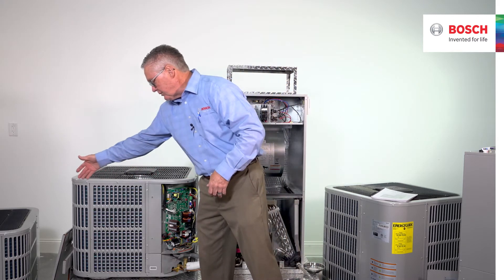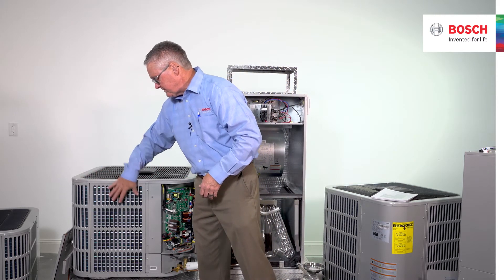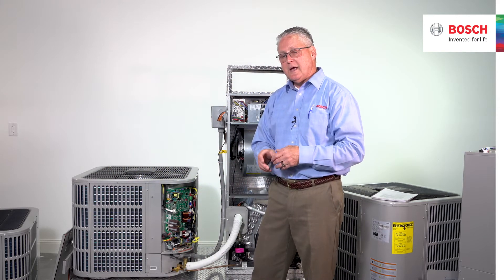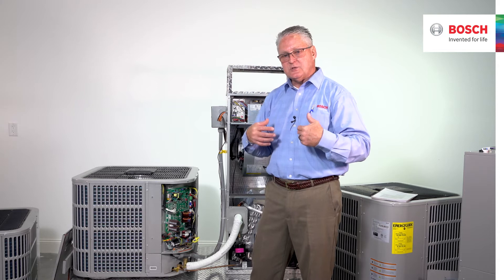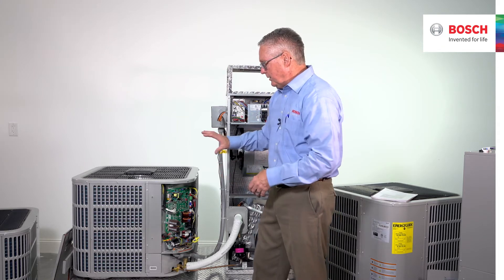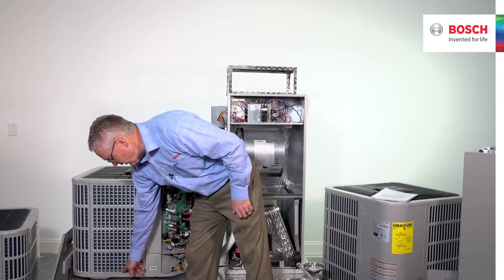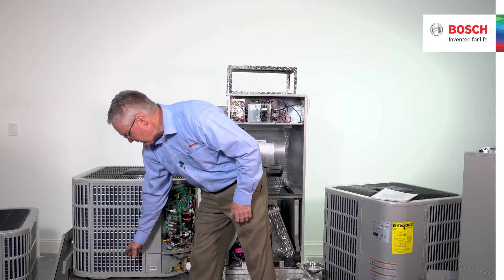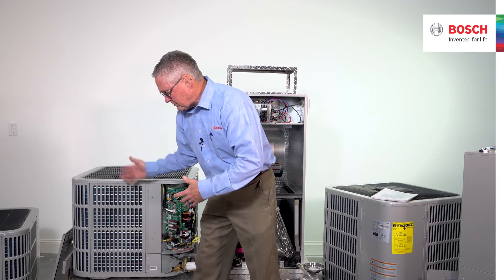If needed, you could run water down through this to clean the coils. But probably the easiest way to do it: put the cover back on, keep the power off, and take a water hose and start rinsing from the bottom up.